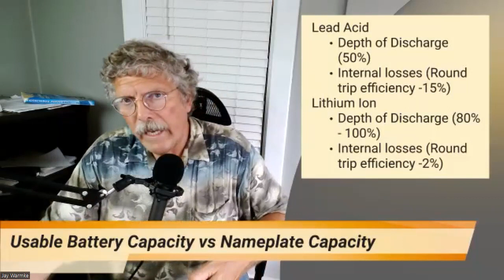So what are some of the other issues there? Well, with lead acid you've got depth of discharge, usually around 50%, whereas the depth of discharge for lithium ion is going to be 80 to 100%. You can sometimes use as much as 100% of the battery. The internal losses, also known as round trip efficiency: with lead acid, you're going to lose 15% of the power going in versus coming out. With lithium ion, only about 2%.